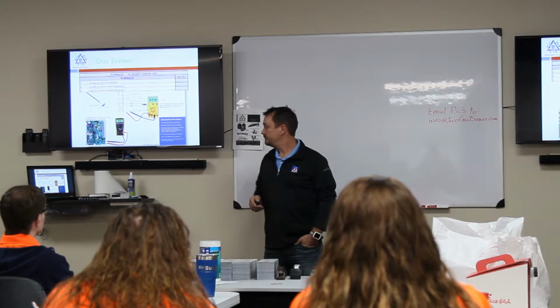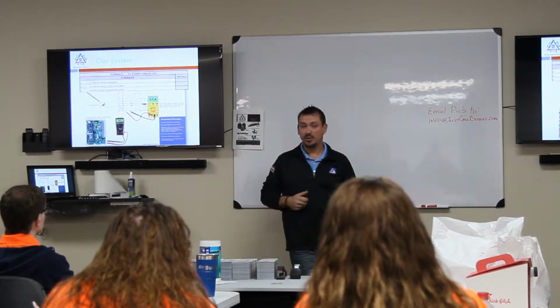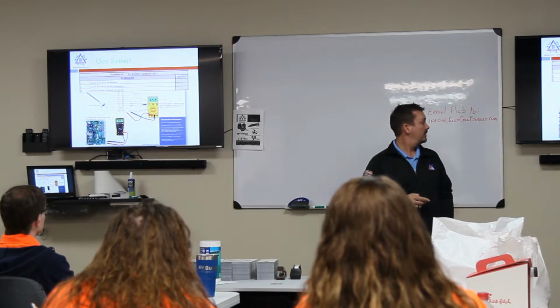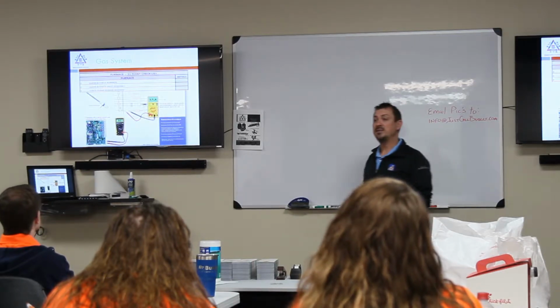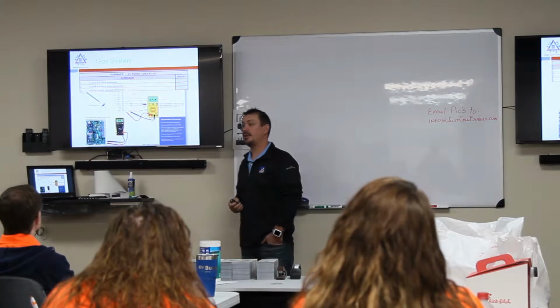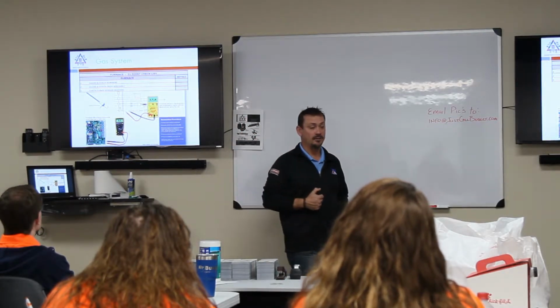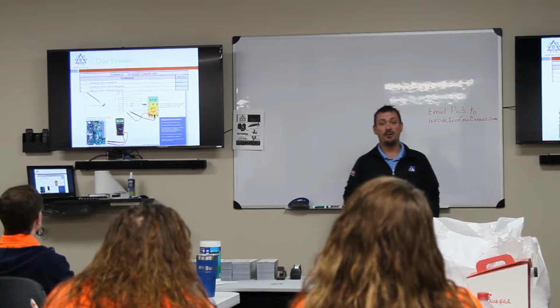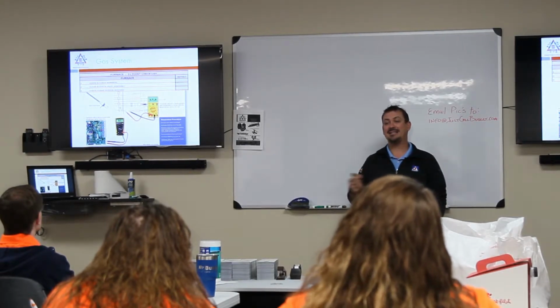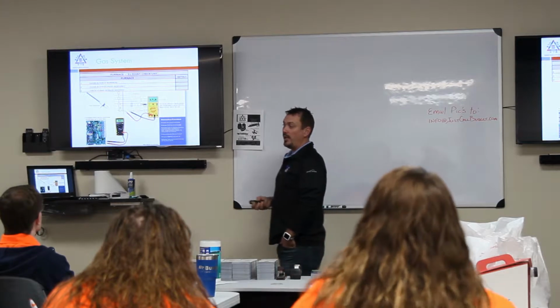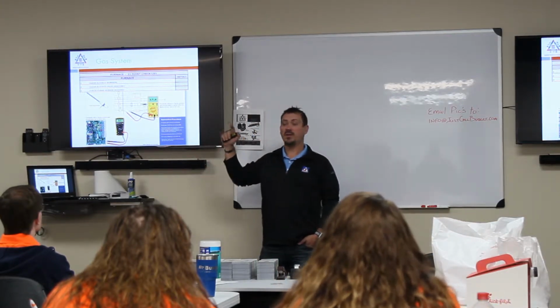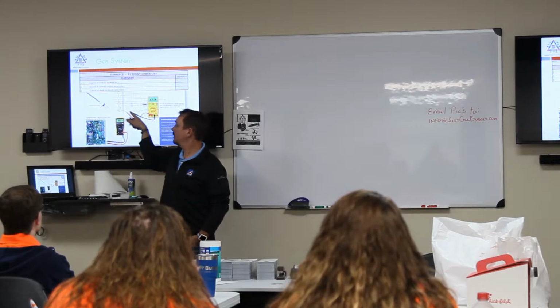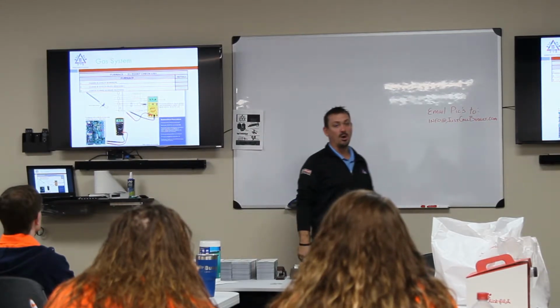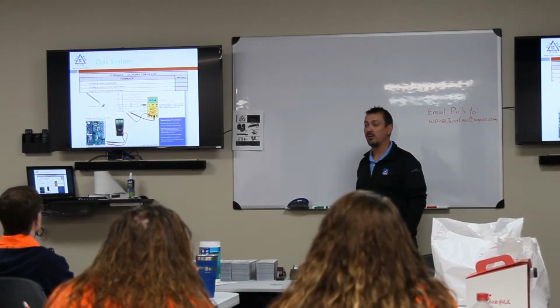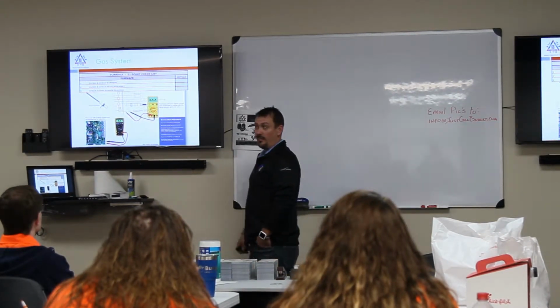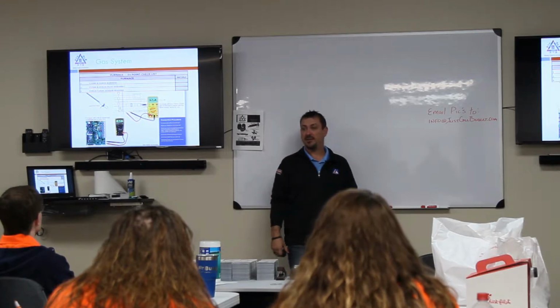So on your flame sensor, we're going to want to inspect the flame sensor. You can take a reading on this and get an accurate reading off of it, and then clean it to see if your cleaning has improved it. A couple of ways to do this: take the flame sensor and unhook it like they're doing right there, and you're going to read microamps. So you're going to need a meter that will read microamps. Above 1.5 is a good reading.